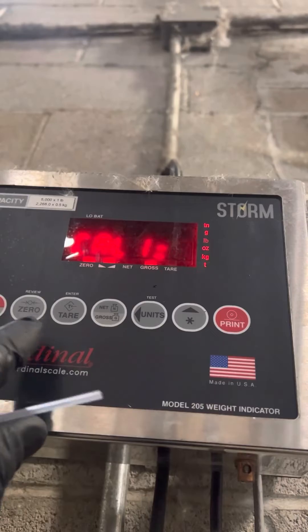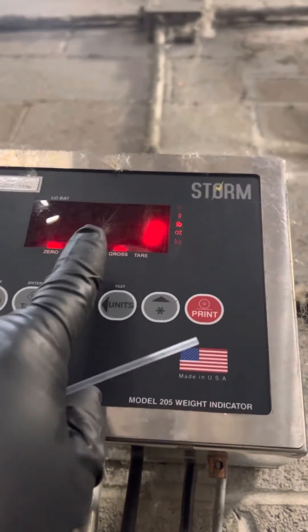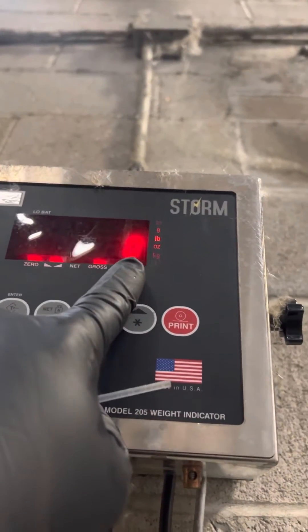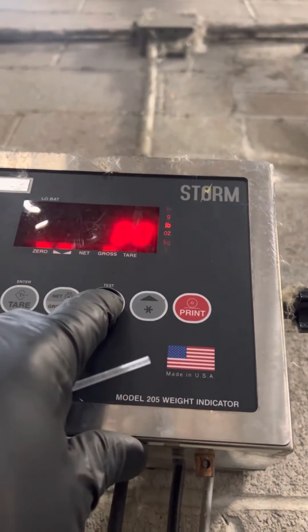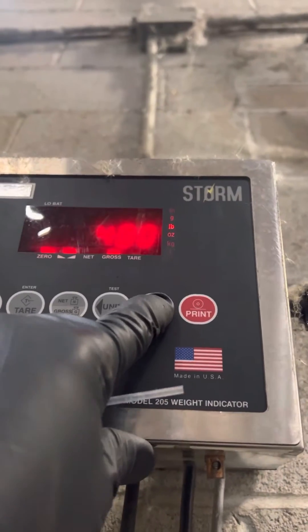CAL 1 — we are going to press ENTER, and then you're going to enter the weight that you're going to use to adjust the calibration. I'm going to use 400 pounds, so I'm going to use this key to go over and then go up.